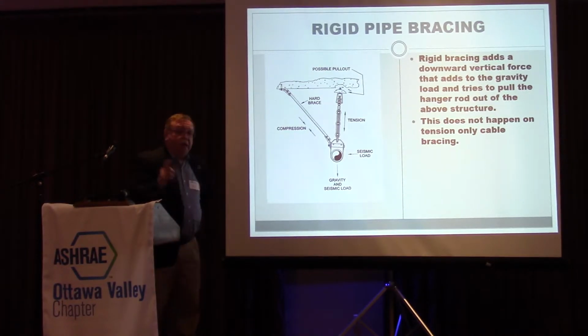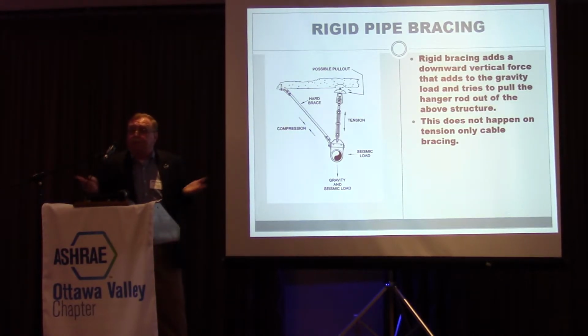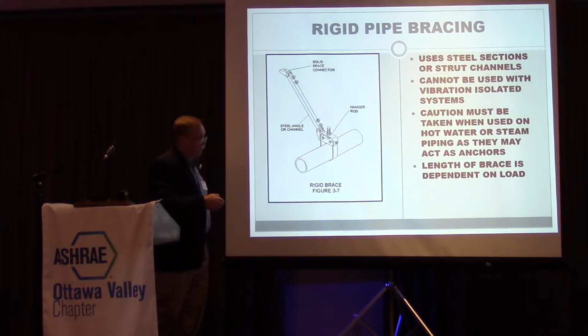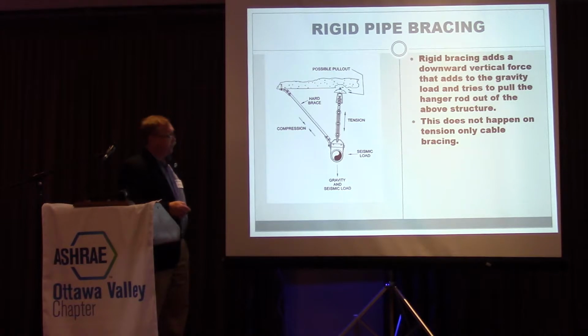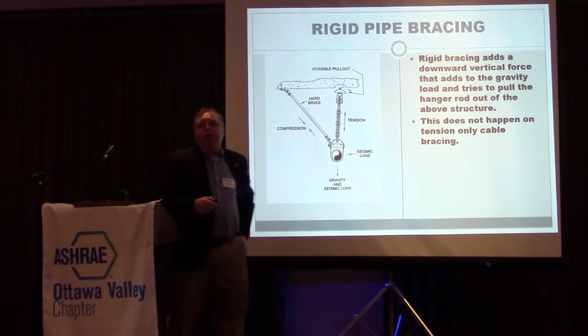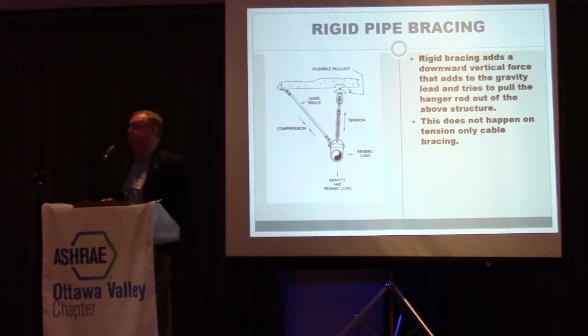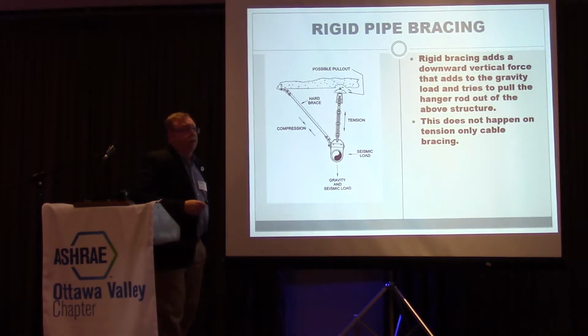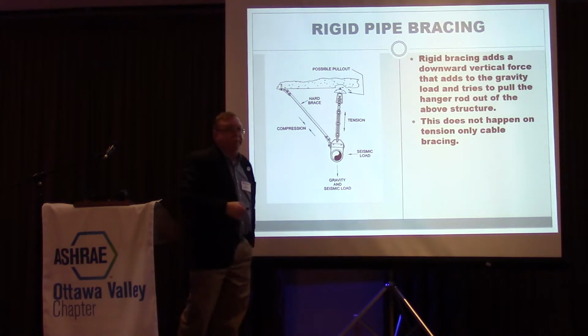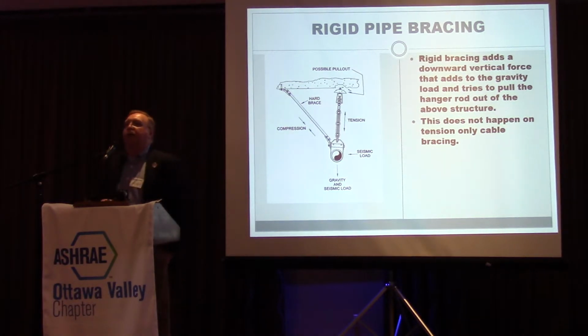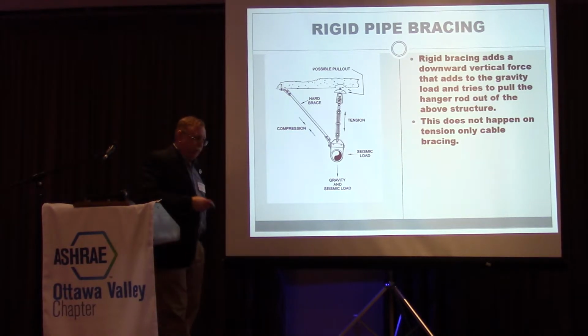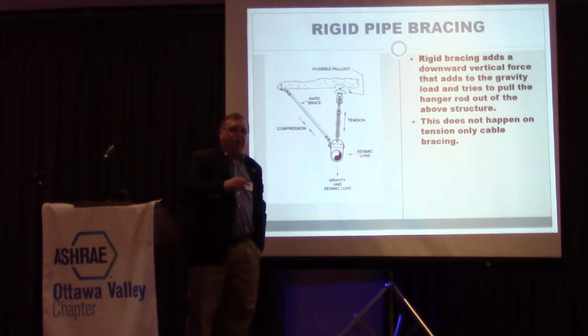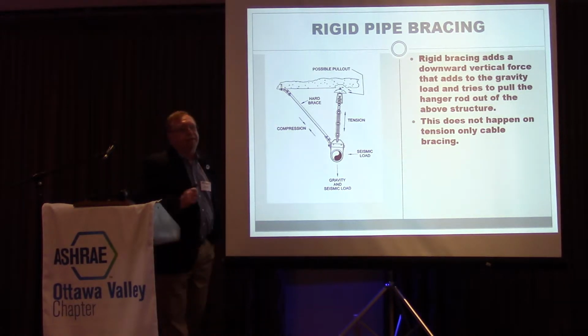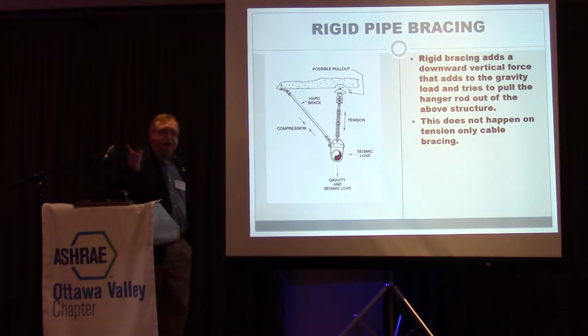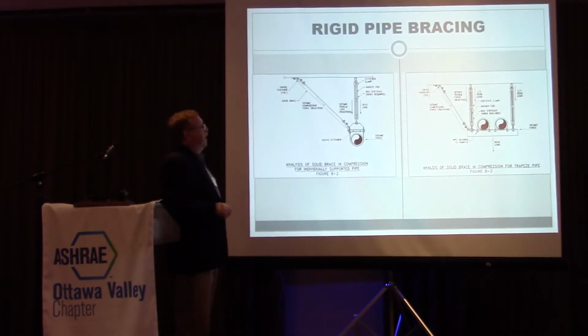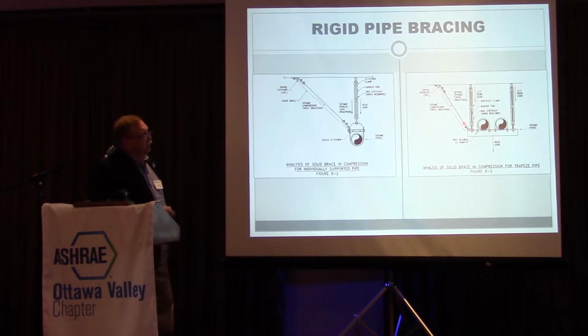We didn't see them in the cable system because the cable system doesn't have that, but in the rigid system we did run into those. With all bracing, one thing you've got to look at is your hot water and steam systems. They are a brace. You put these in and it stops the pipe from moving, that's the basic idea. So you have to work in conjunction with the mechanical engineer to make sure you're not screwing up where he plans that pipe to move during its lifetime. You've got to work out the bracing so he's happy and you're happy. And if you have a trapeze, it's basically the same thing.